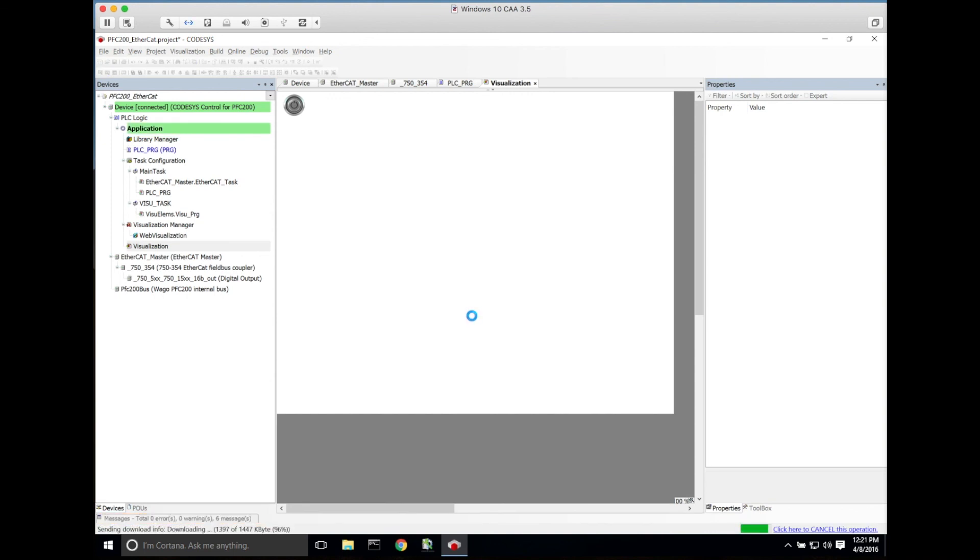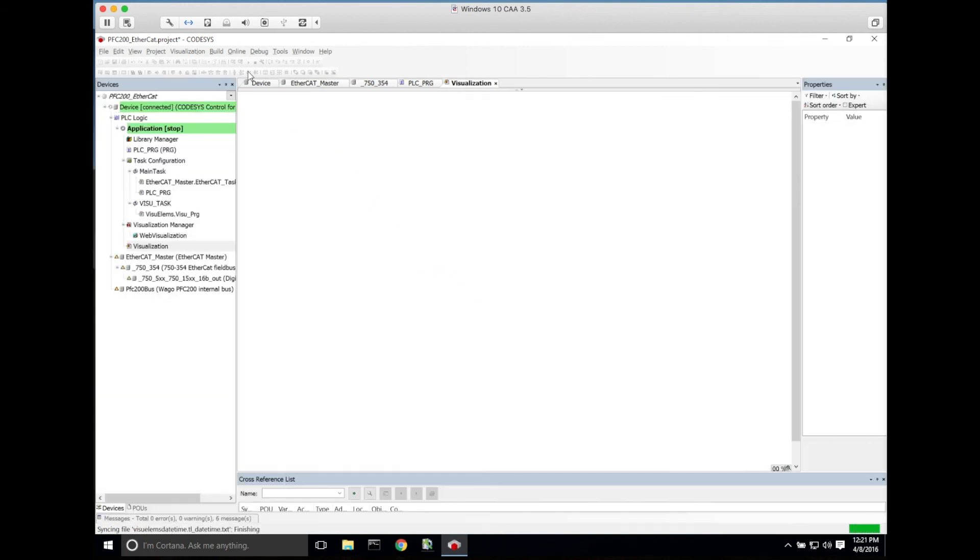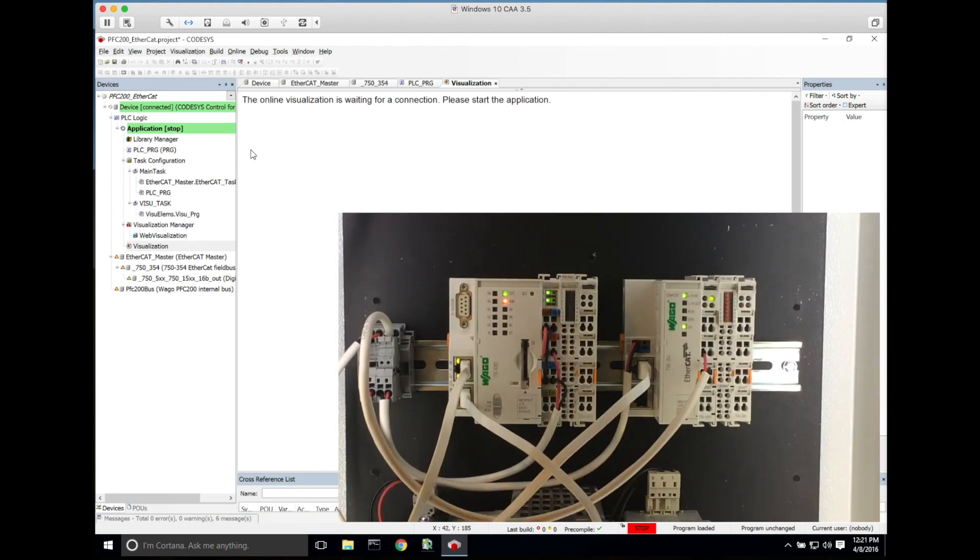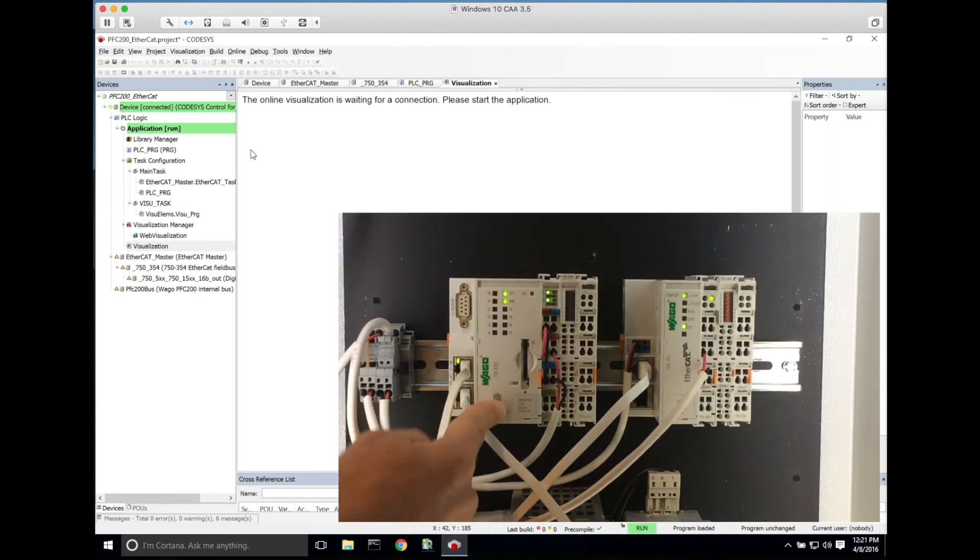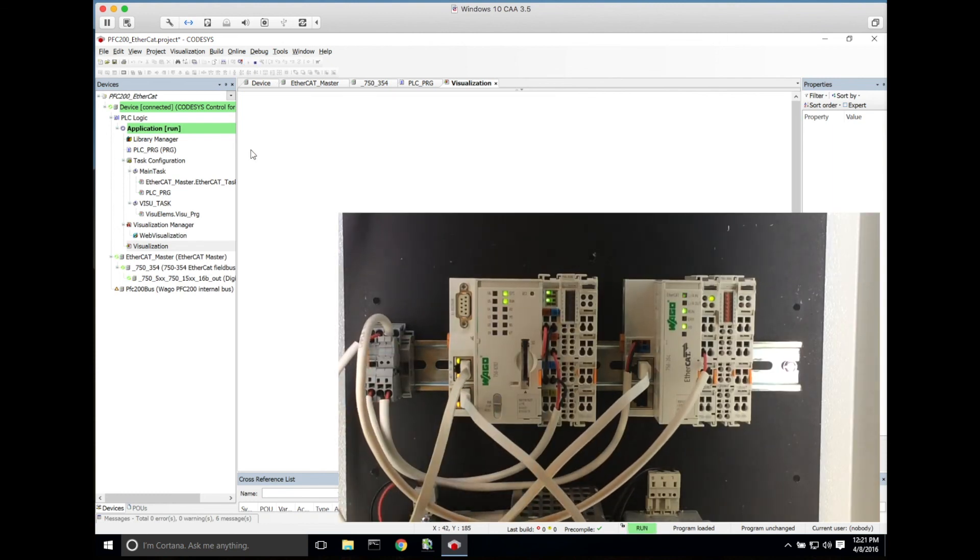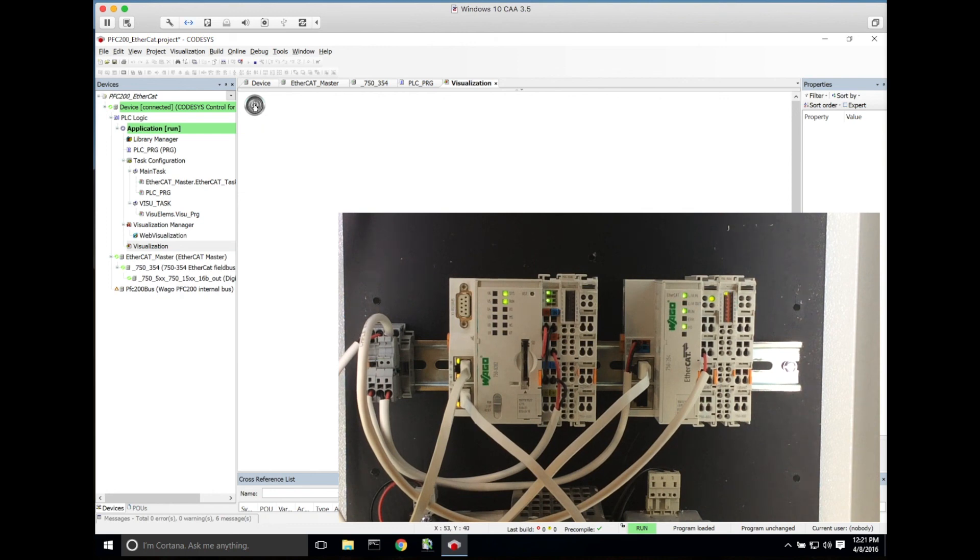Once it's downloaded the project, we will switch this into run on the face of the PFC200, since we have the switch in the stop position. Once we go online, you can see here from the visualization that we're able to toggle on the first output of the EtherCAT coupler.